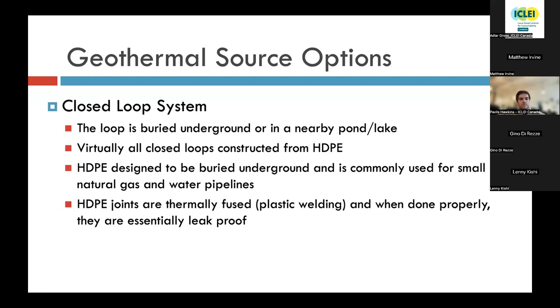So a closed loop system is one in which the loop is buried underground or in a nearby pond or lake. Virtually all closed loops are constructed from high density polyethylene, plastic pipe, or HDPE. And this HDPE pipe is designed to be buried underground and is commonly already used for natural gas and water pipelines. And then HDPE joints are thermally fused. It's basically plastic welding. And when done properly, they are essentially leak-proof. Much the way when two pieces of steel are welded together, the weld becomes actually stronger than those two pieces of steel. Likewise with thermally fused plastic, that joint is actually stronger than the pipe that's being fused.